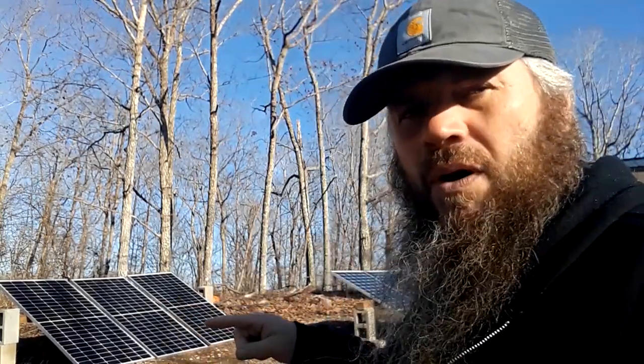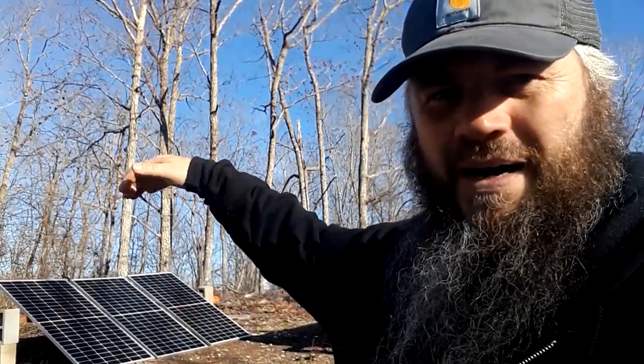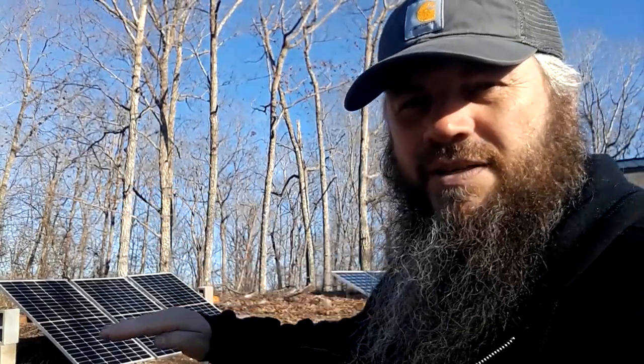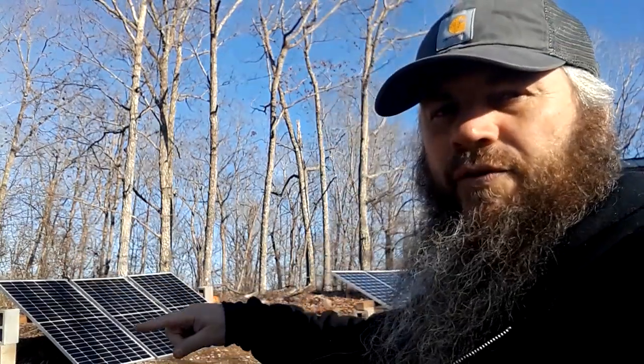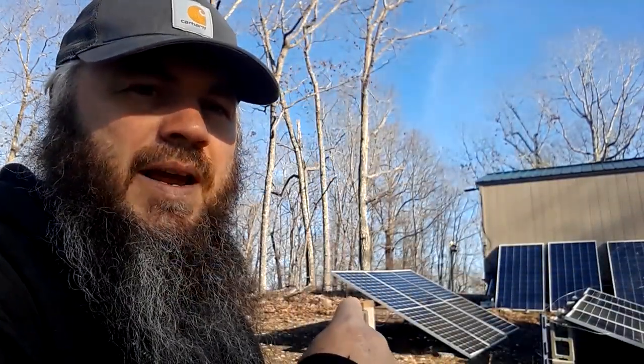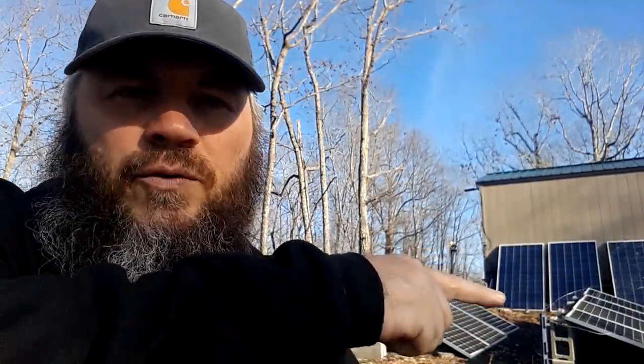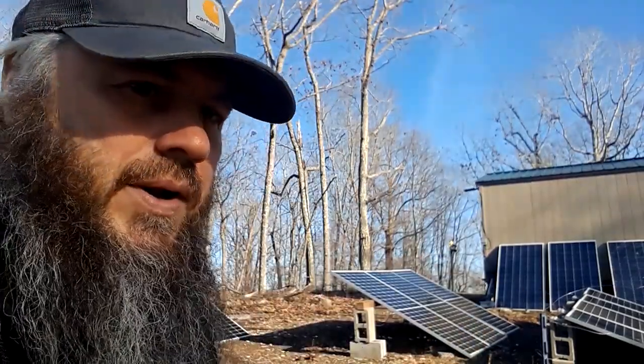So what we do with these panels is protect them with the DC breaker box that is behind there. Each series of panels has to go into one breaker. For these 3 panels, I have a 15 amp breaker, 15 amp breaker, 15 amp breaker, and for those 4 panels, I use a 20 amp breaker. So that's my first stage in protection.